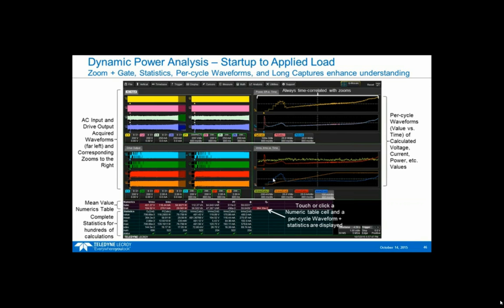But there are some things that change a lot. Here's the drive output voltage, the RMS drive output voltage ramping up, hitting a steady state. And then here is where we put the load on, and you can see the current starts to ramp up. This is the peak current during the startup event on the drive output. And what's interesting is the peak current on the drive input happens quite a bit earlier as well, when the drive is first started and you're charging the power electronics section to some extent.